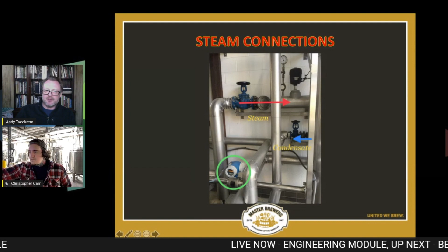I also circled in green there, we have a mag meter on the wort side. And that's just to let us know how many gallons per minute or gallons per hour the pump is providing for the wort circulation. So it's such a nice feature. If you have a single speed pump, you probably wouldn't need that. But in our case, our pump's doing double duty, so knowing that flow rate is pretty important. This steam is low pressure steam, by the way, and that's another nice thing about these. This whole system runs on 15 psi steam. So that means you don't need an ASME rated heat exchanger or any kind of fancy extra engineering stamps. And it means most of us that have steam are going to have at least 15 psi available.